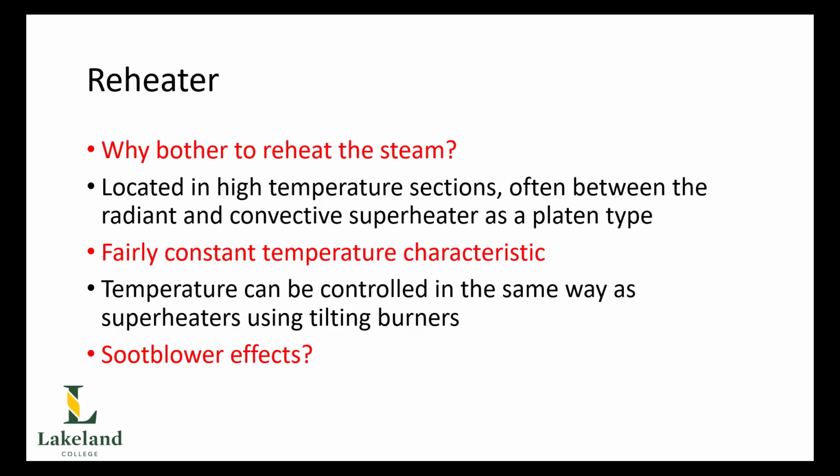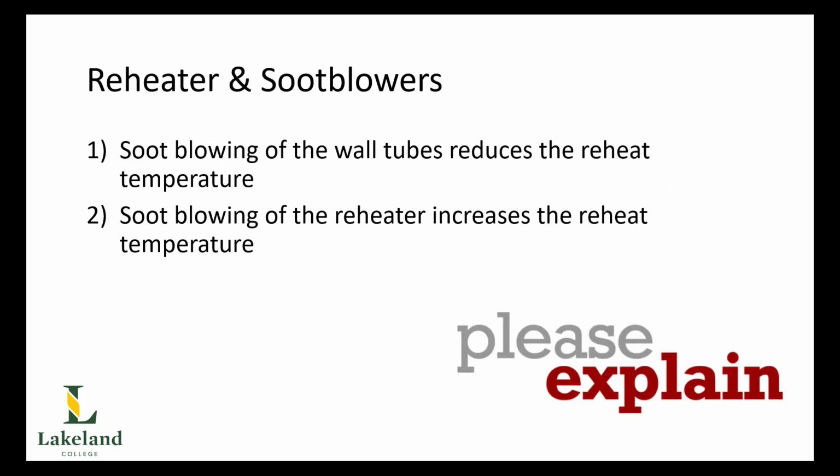Now, the last thing that we need to mention is what effects would soot blowers have? And this is going to be soot blowing of the reheater itself and also soot blowing of the radiant section. Now, there are two effects to be noticed from doing each of these soot blows. The first one is that if we soot blow the radiant water walls, then we're going to reduce our reheat steam temperature. Now, why is that?